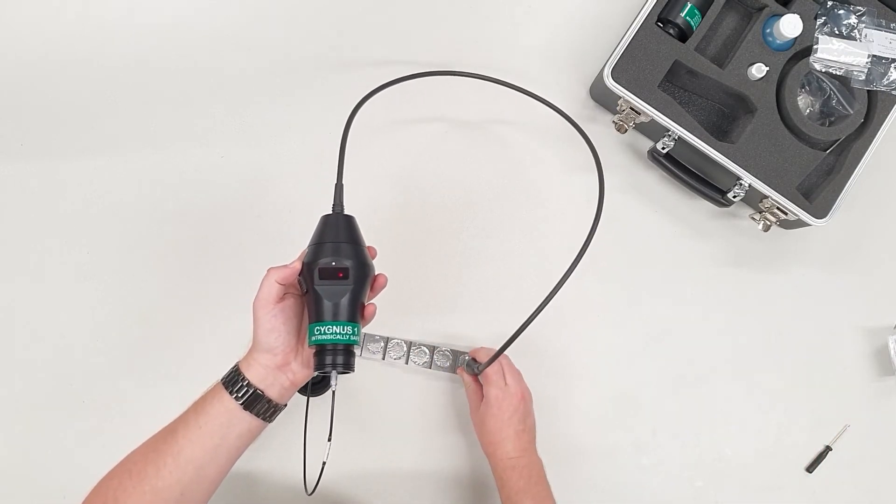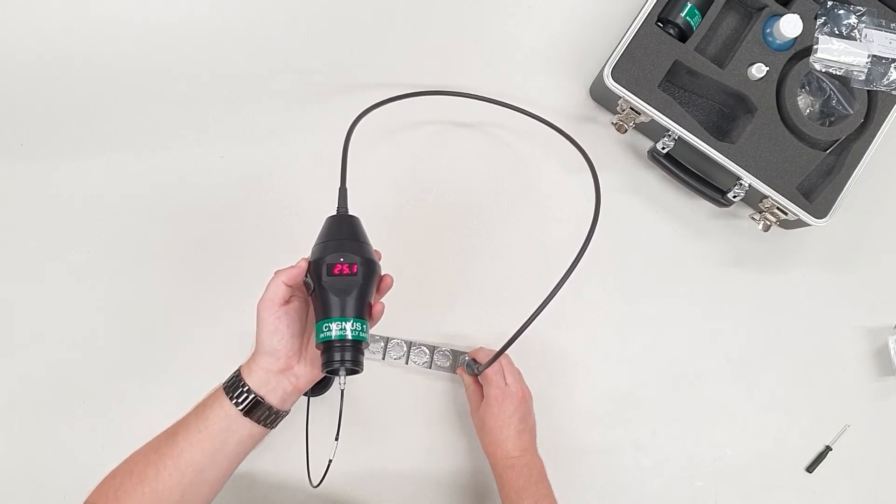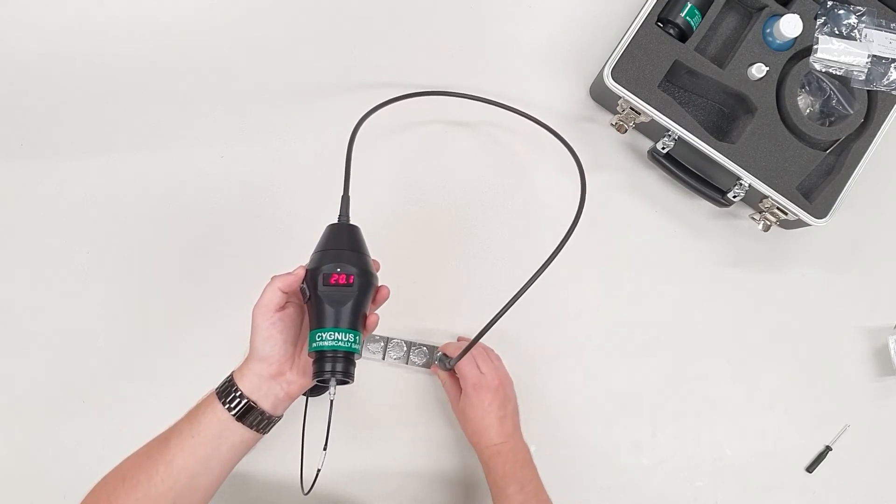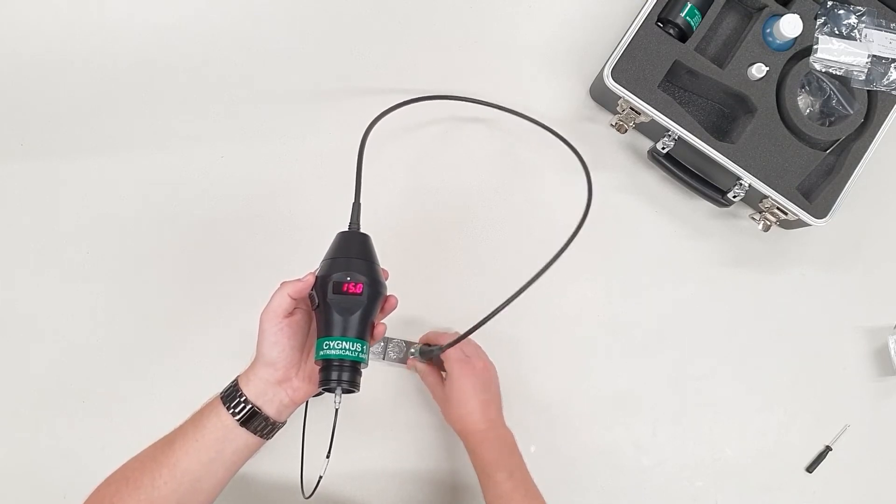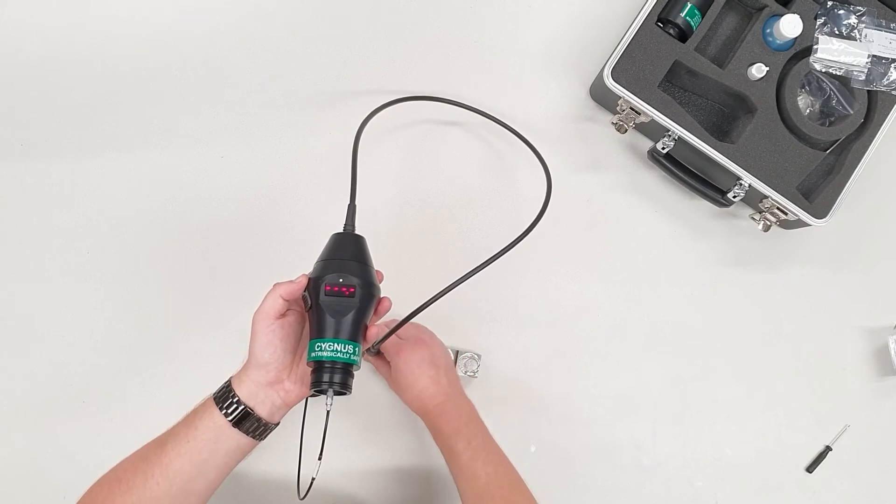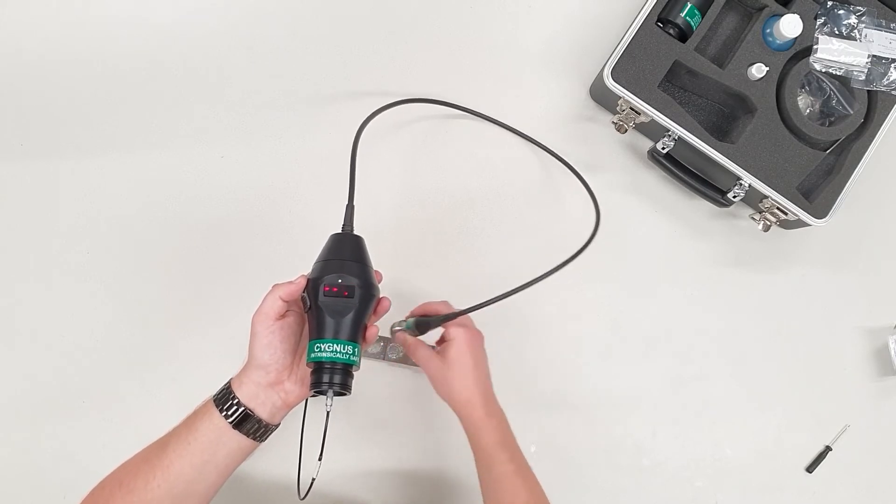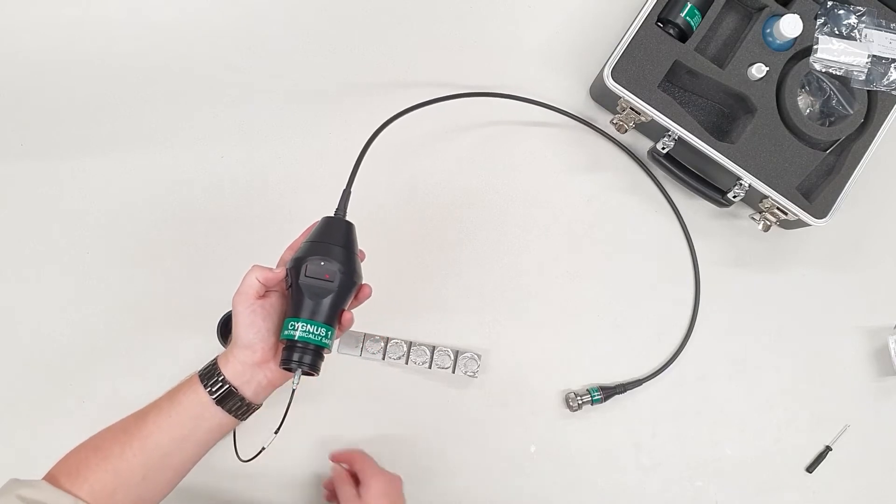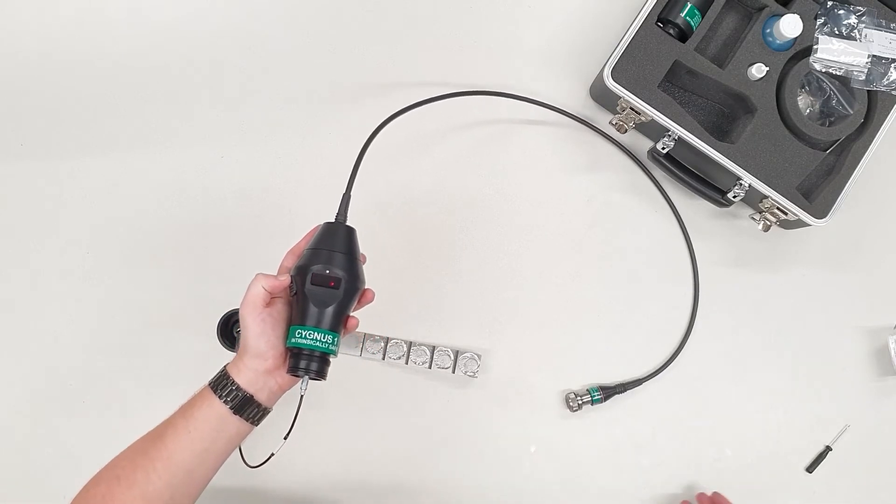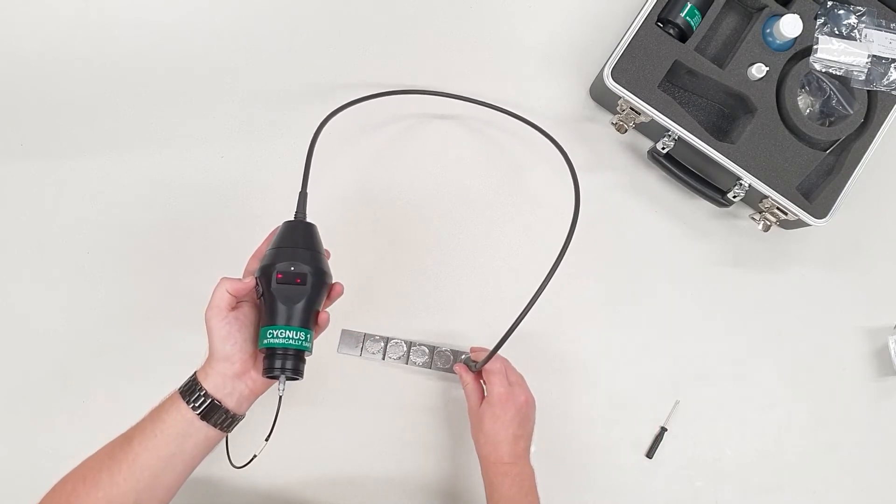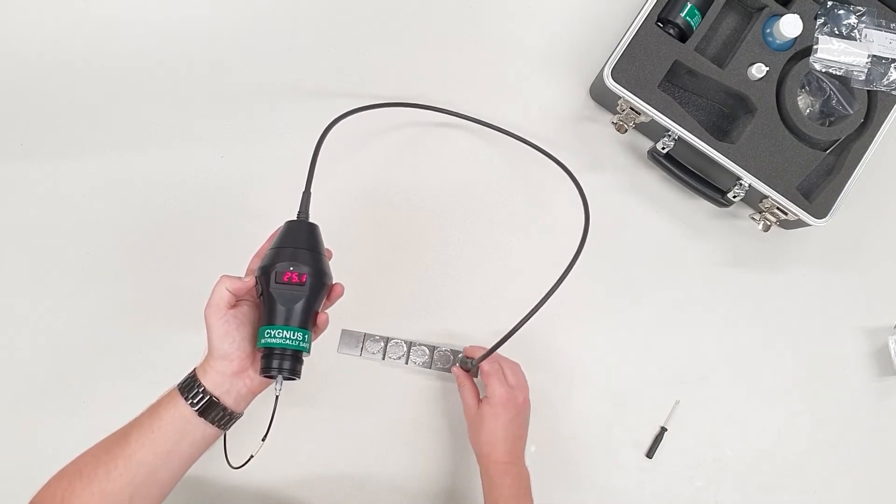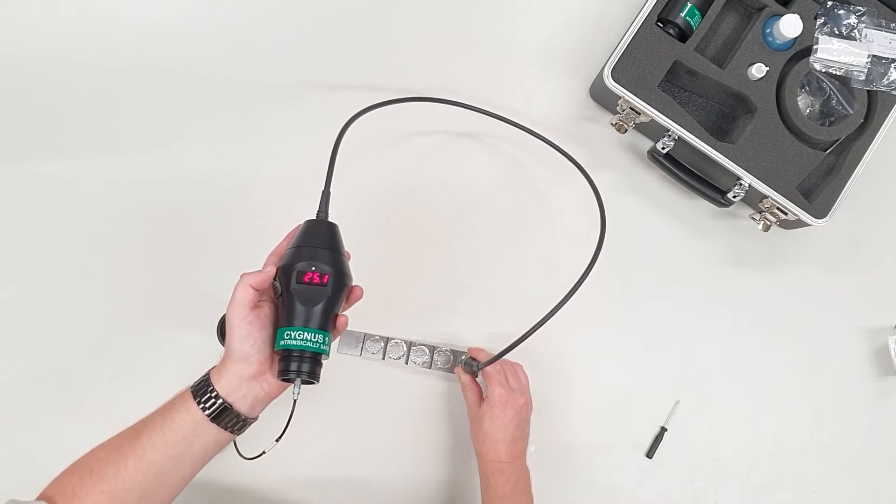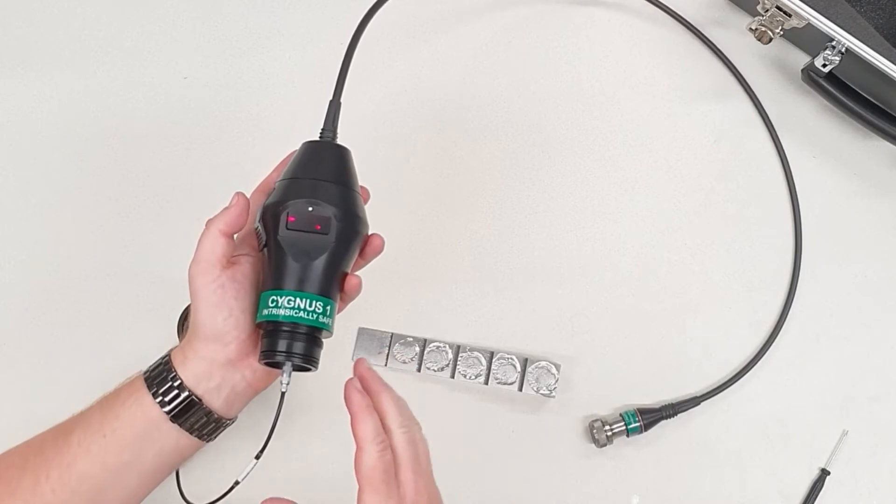Now I can take a few reference readings on this block. This should read 25, yep, it's simply a rounding error, 20, 15, 10, and 5. If I didn't know the velocity of the material, I can calibrate to a known thickness. It's a very similar process, just a matter of putting the probe on the sample and adjusting the screw until you get the right thickness you're looking for.